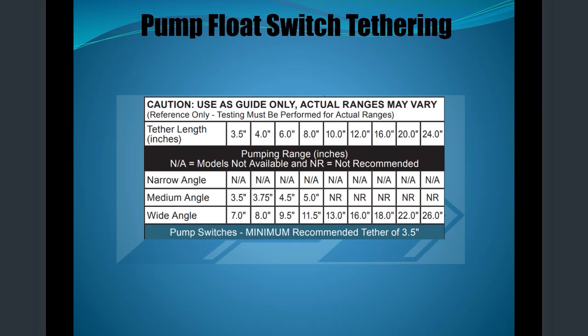Here's a tethering guide that tells you, based on how far you have your tether out, what you get. If it's 3 inches and it's a narrow angle, well, we're saying that's not available. 3 inches and a medium angle: if you tether at 3 inches, a medium angle float switch would be a 3.5 inch pumping range. So over here on the left, if it's 3.5 inches at a wide angle, that's a 7 inch range. And if you go over, let's say 10 inches, let's go back down to 8 inches because it's not rated for the medium angle. So at 8 inches, it'd be 5 inches at medium angle or 11.5 at wide angle.